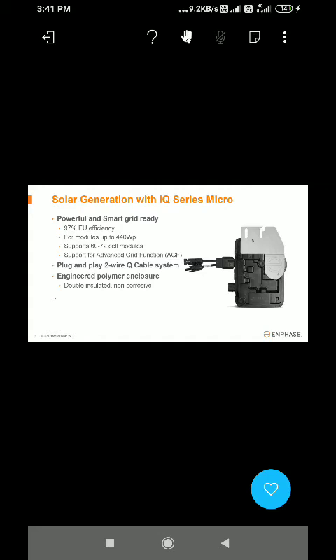And so, regarding insulation resistance and leakage to any functional earth or signal connections of such appliances, products of this type are required to be labeled class 2 double insulated. So if you see this on the data sheets, you can see the level of class 2 double insulated, and that's why we say you don't require any earthing of it.